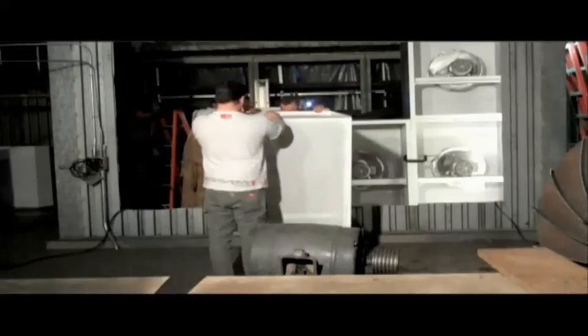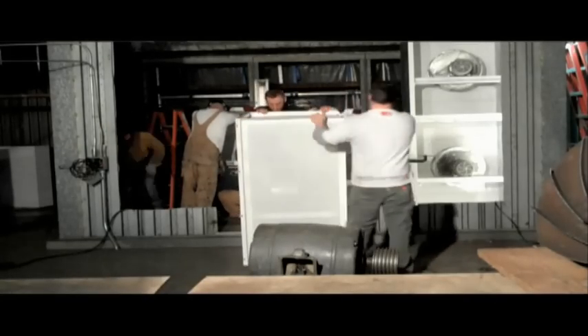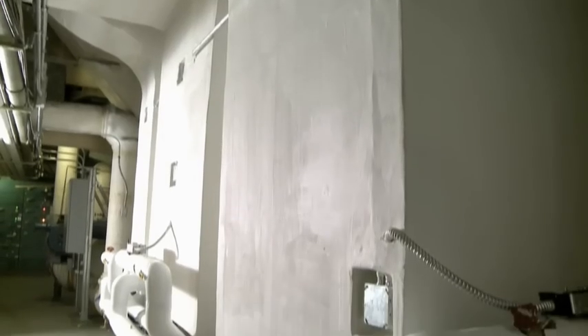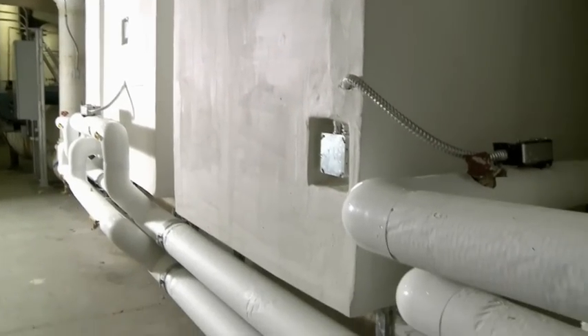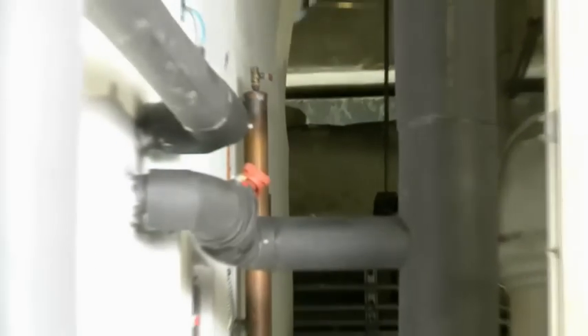We were comparing the FANWALL retrofit to a complete changeout. Again, it was an easier installation and it seemed to fit our needs better. With the retrofit, we were able to change the configuration of the air handler from a constant volume to a VAV system, offering significant optimization of energy control. We also added a CO2 monitoring system on each zone so we could override the outside air control dampers for demand control ventilation needs as required.